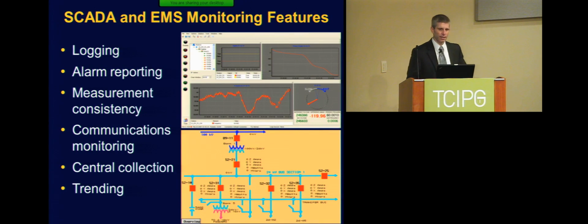At the EMS or SCADA level, we have logging at a wide level. We have alarm reporting, where alarms come in from multiple sources, and measurement consistency - another benefit since our systems are over measured. At the SCADA level we take in measurements like synchrophasors and metering and do a consistency check to make sure the system agrees that voltages are what voltages are, and current flows are what current flows are.